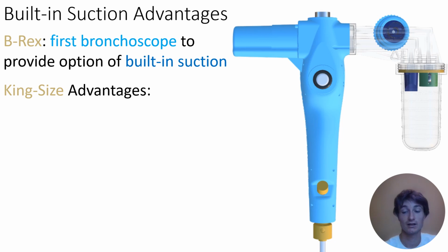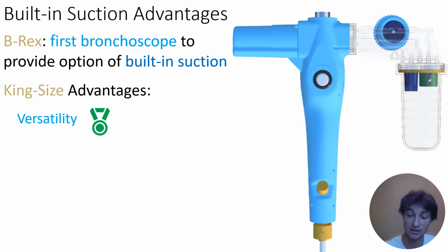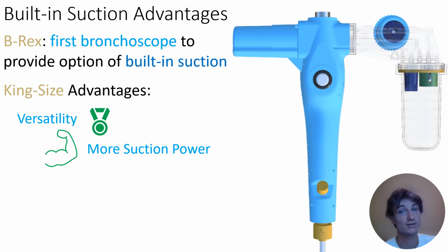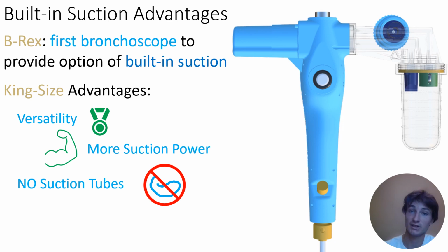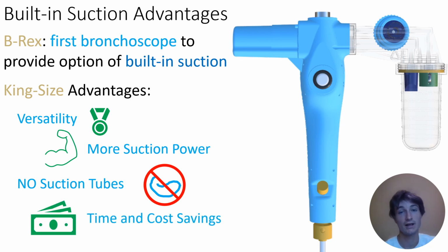So for the built-in suction, this provides an added level of versatility. The clinician can choose whether to use the built-in suction or just keep with the hospital wall suction. It offers more suctioning power because the length of the tubes is reduced, and therefore there is less fluid resistance. Because there are no suction tubes, it also means that the clinicians are not impeded in their movement in the workspace. There have been many reported cases of clinicians tripping over tubes and suffering severe injuries. In addition, with built-in suction, you save time and costs. There's less pre-procedural setup, and less maintenance and sterilization required for each procedure. This saves hospitals time and money.